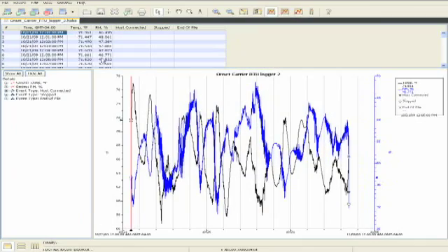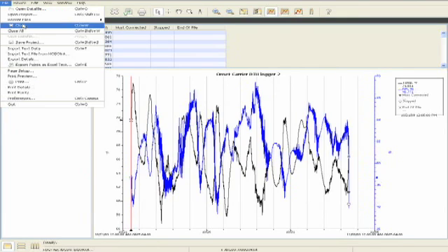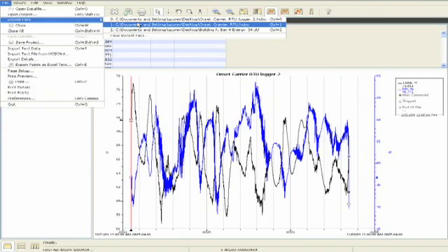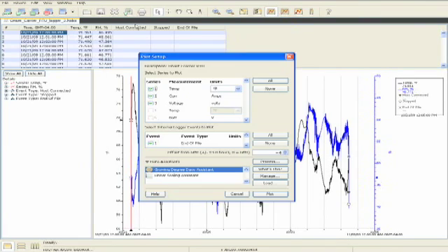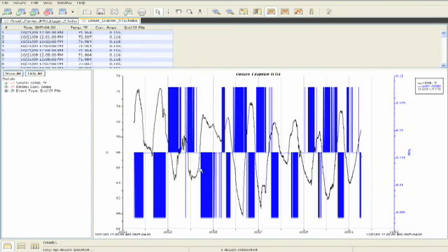Hi, this is Scott from Mercury Mechanical. We're down here in the office to check out the results of our two data loggers that we had on a Carrier rooftop unit. And we have our two files saved. This was our first logger with our supply air temperature, and our amperage and voltage is listed here, but we did not use that, so I'll uncheck that. And then we hit plot to see our graph.